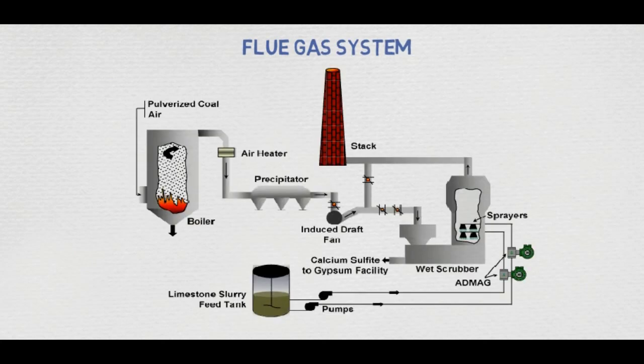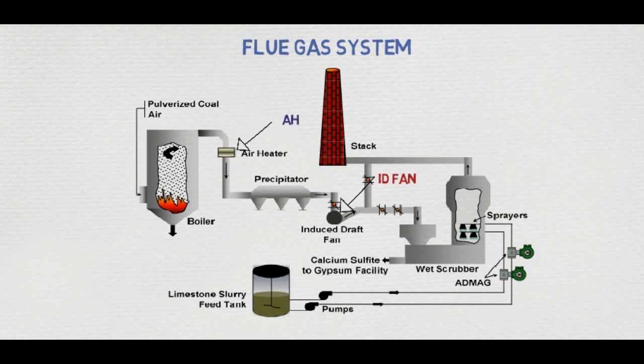This shows the flue gas system. When combustion takes place in the boiler, it generates ash and flue gas. The flue gas is sucked by the ID fan — the induced draft fan — and passes through the air preheater and then to the ESP, the electrostatic precipitator. Here, the dust particulates are collected, and the rest of the ash is fed into the wet scrubber through spray nozzles and goes to the slurry feed tank. The flue gas is exhausted through the chimney.